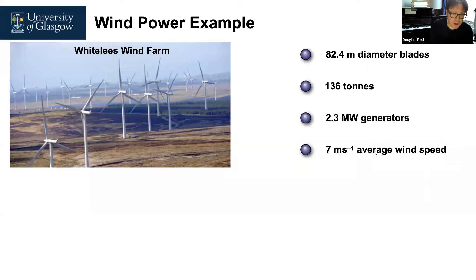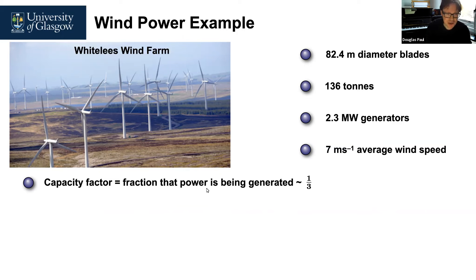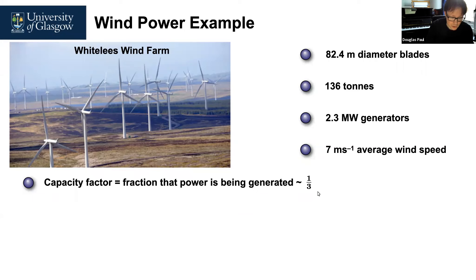Whitelees has a visitor center with a lot of data on electricity generation at the site. Regarding the question about capacity: the capacity factor has to be measured locally, wherever your wind turbines are. At Whitelees, it has typically run between 27 and 33 percent each year. For the calculations here, we'll be generous and use 33 percent throughout.